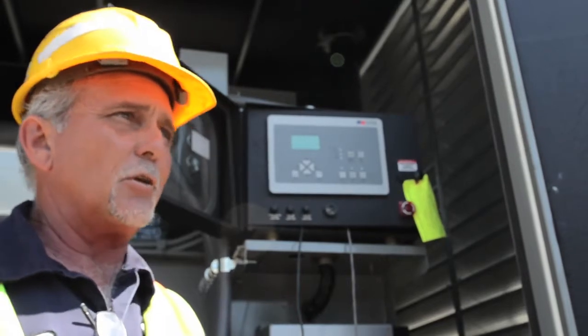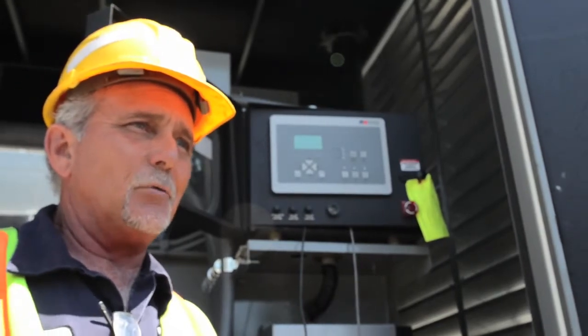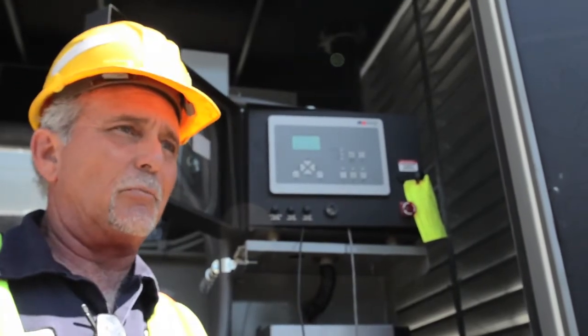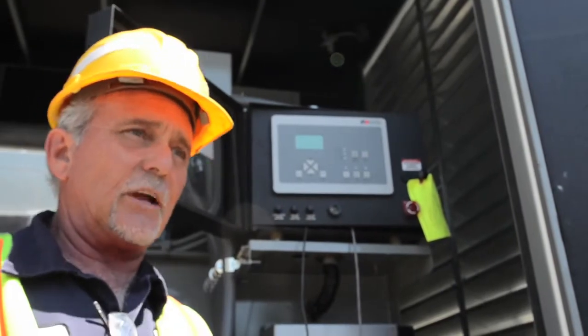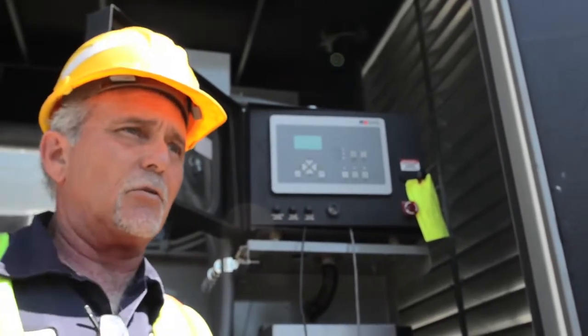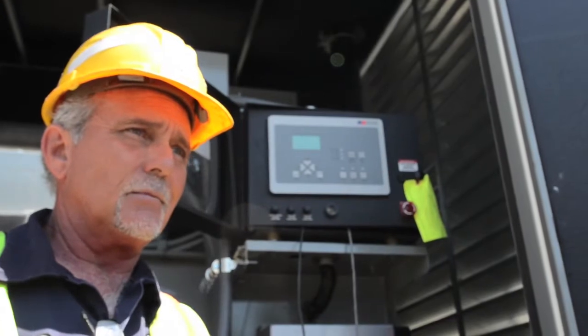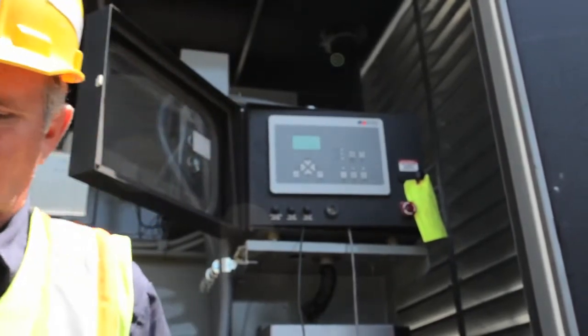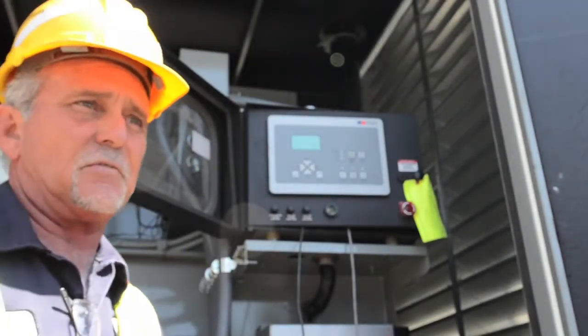Then everybody wants to come out and do a load bank test on your generator. What that does is it forces the turbo to build full boost pressure. It pushes the rings out, cleans all the stuff out, and blows all the garbage out of the muffler. So it's not good to run them unloaded for lengths of time.